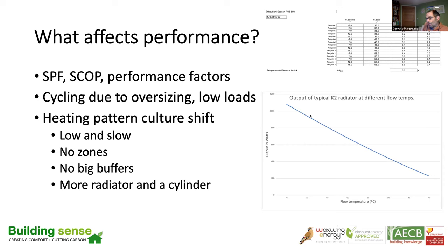And when we move over to a heat pump strategy, we're going to go for what I've heard described as low and slow, where the radiators could be described as warm rather than hot, but they're on for a lot more of the time. There aren't any zones, so you don't turn rooms totally off that you're not in. You just heat them to a slightly lower temperature. We don't have big buffers, which we don't currently have in our homes, but in other heating strategies they are used.